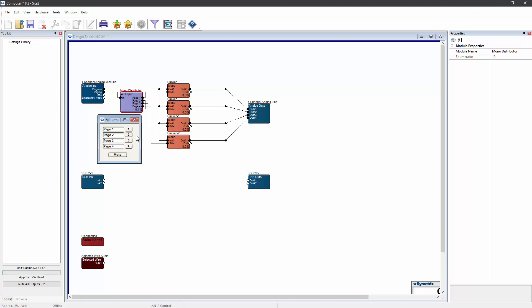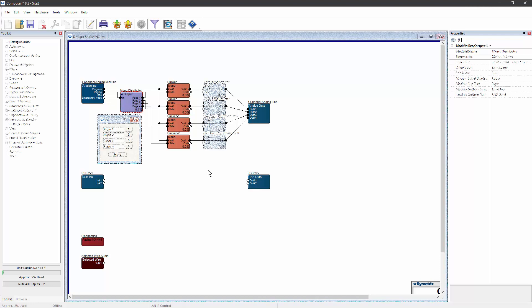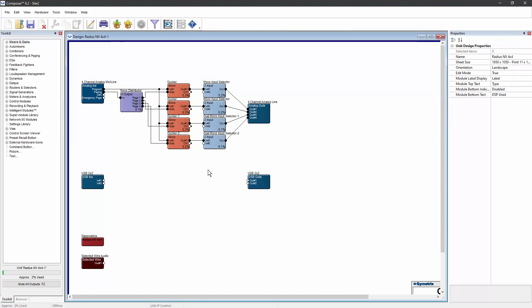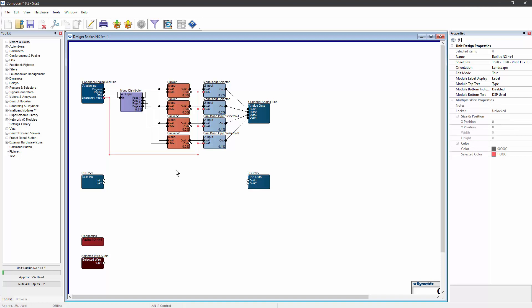In some cases though, you also want to have emergency paging. One simple way to accomplish that is to place an input selector on every output from the DSP. One of the inputs on the input selector is wired to the normal signal path for that output, and then the other input on every input selector is wired to the emergency page input.